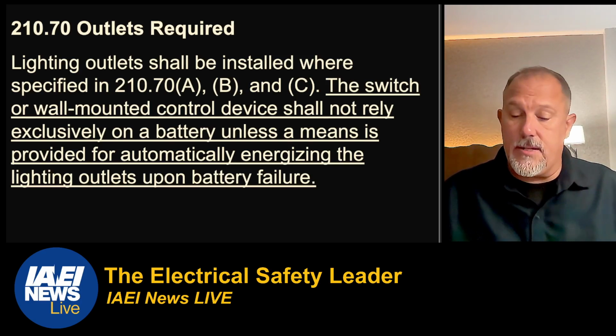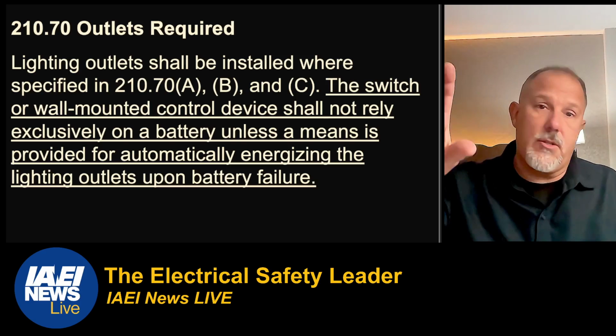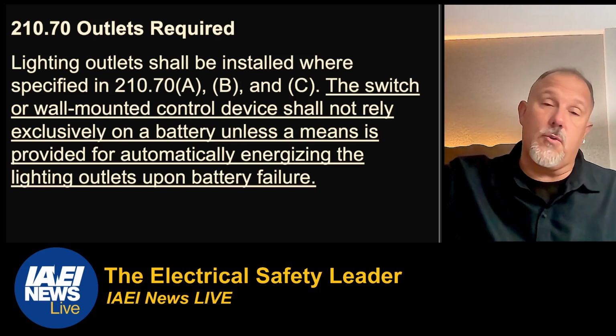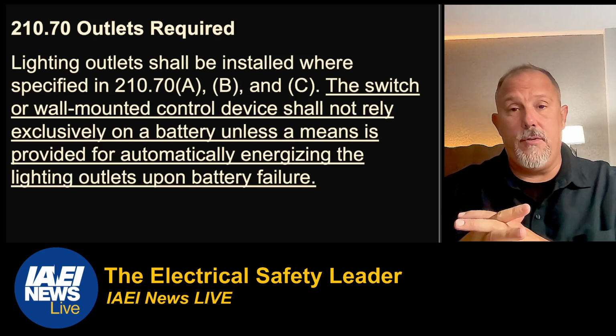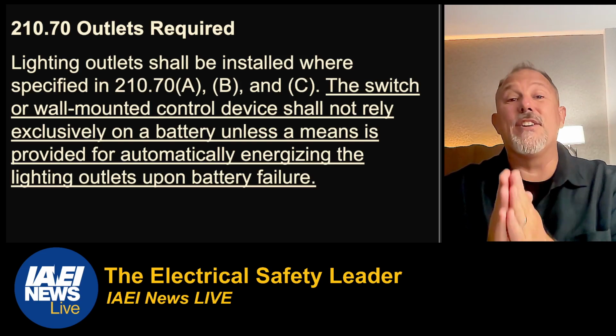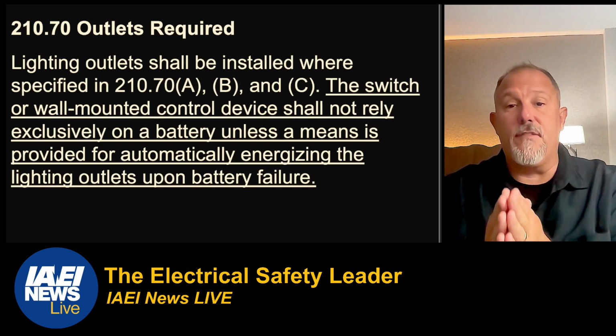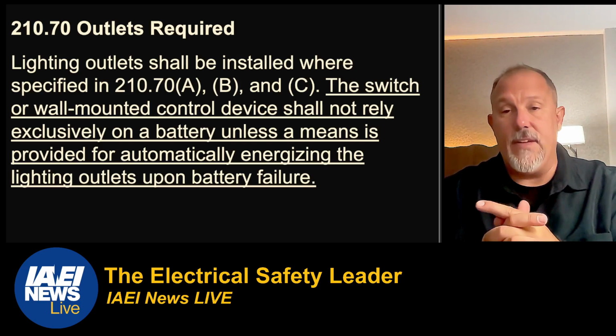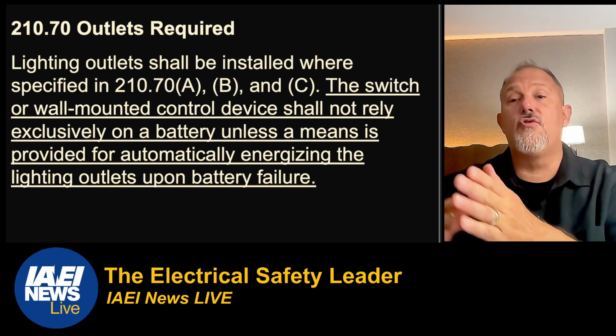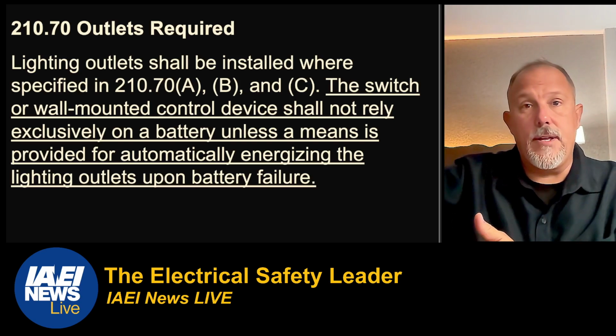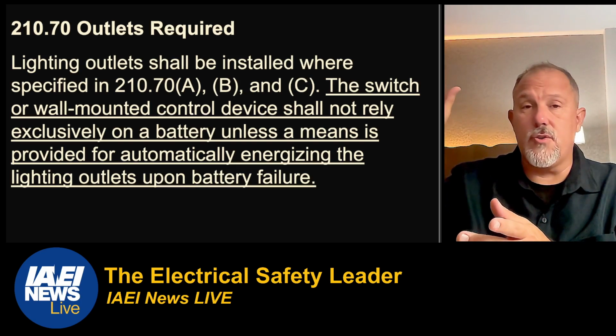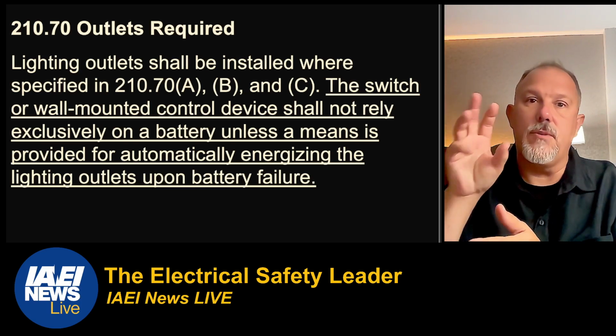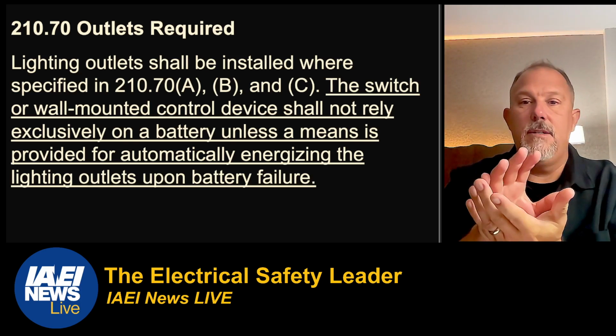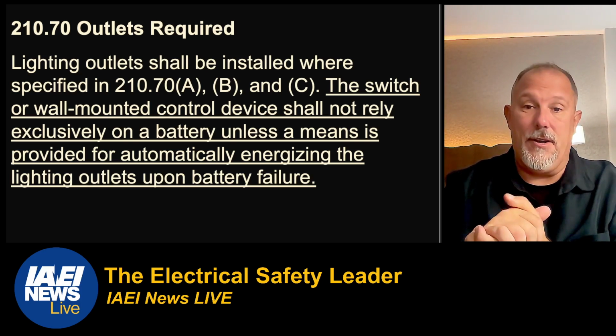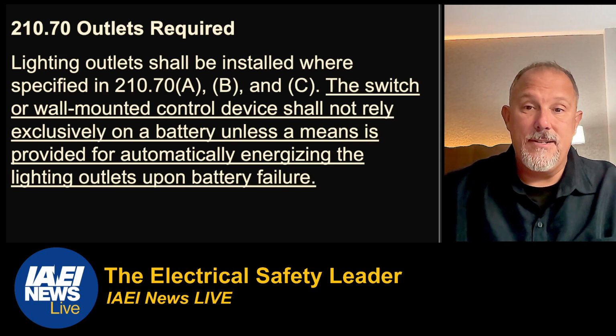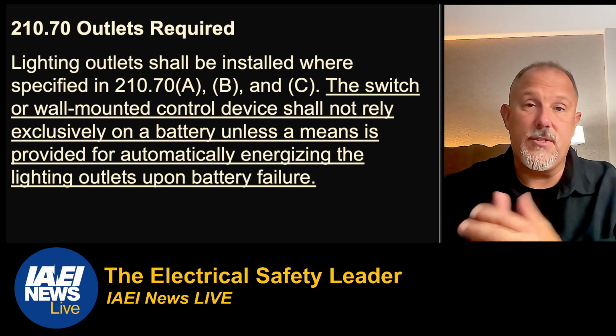Based upon what we did in the last cycle with 210.70, you could just put a wireless device, glue it to the wall, not pull a wire to an outlet box behind it, and that controls your lights directly. The concern of the panel was they didn't want to go there, so they said that the switch or wall-mounted control device shall not rely exclusively on a battery unless a means is provided for automatically energizing the lighting outlets upon battery failure. So this is going to drive, in my opinion, the hard wiring. So if you do have a control device that is remotely controlling that light, you're still going to bring the wires down to a switch, because that controller probably relies on a battery as the means to turn something on and off, and they did not want to rely on it.